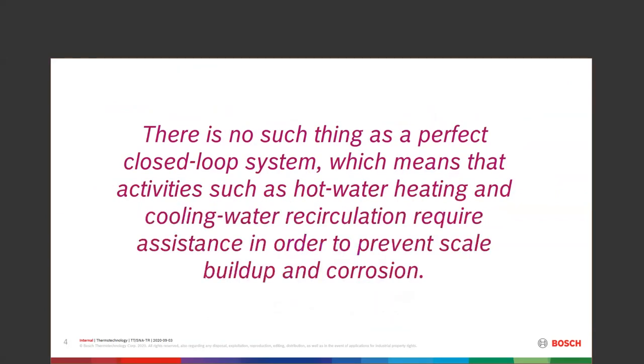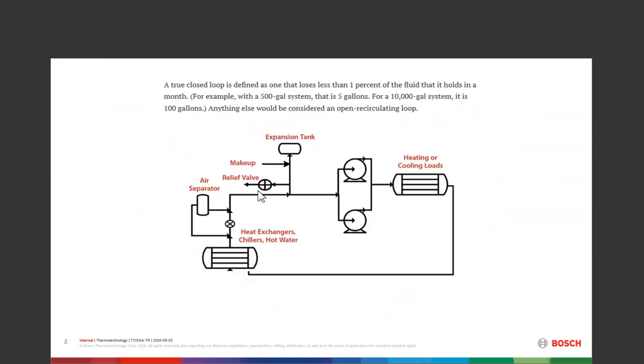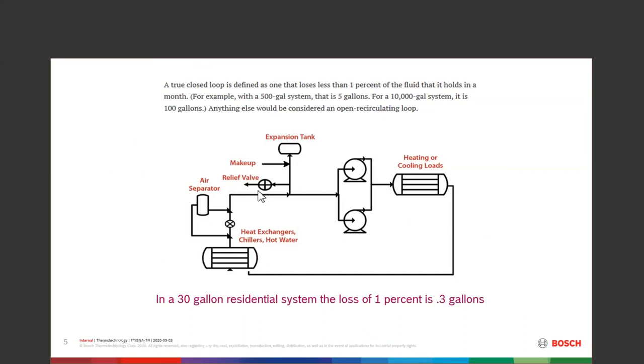There's no such thing as a perfect closed loop. Anything that does hot water heating, cooling, or recirculation requires some sort of assistance or treatment to prevent scale buildup, corrosion, and to keep efficiencies up. If we try to define a true closed loop system, it's one that loses less than one percent of the fluid it holds in a month — so a 500-gallon system loses five gallons a month, a 10,000-gallon system loses 100 gallons a month.